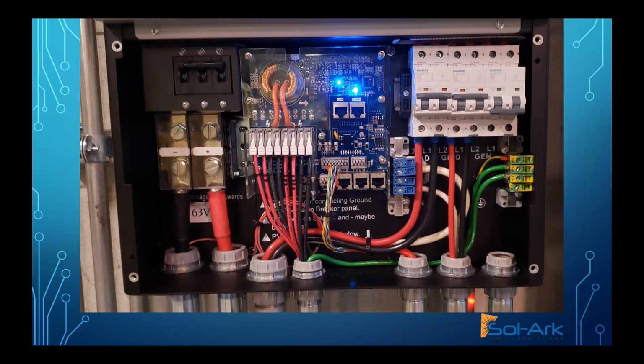If you notice the motherboard there in the middle, the Sol-Ark inverters have CAN bus, Modbus, and RS485. With those 3 communication protocols, we can talk to generators, we can talk to battery management systems. We'll talk more about that. We have full communications established with a number of popular battery manufacturers, and we can talk to Sol-Arks if we want to start stacking them.